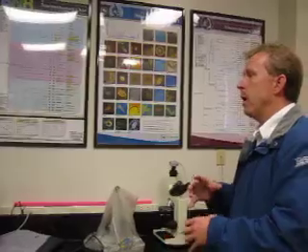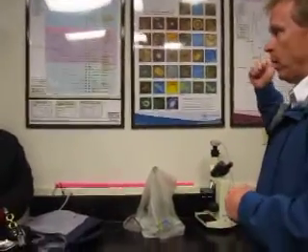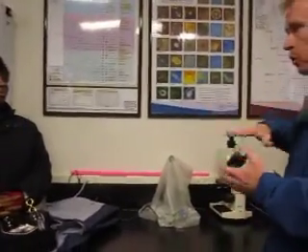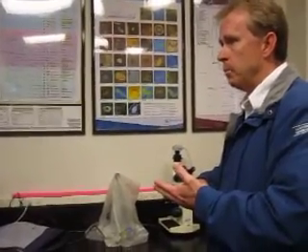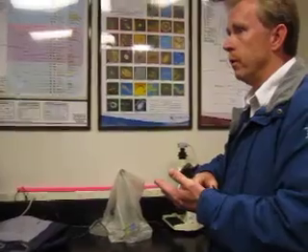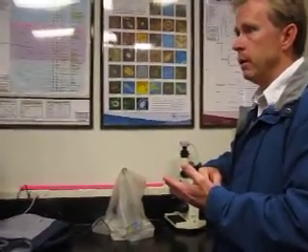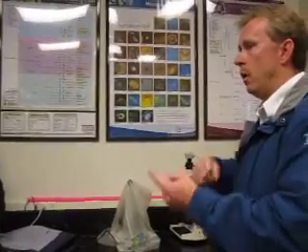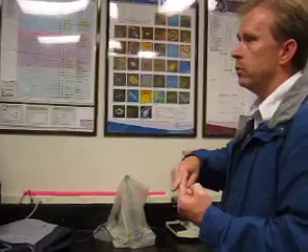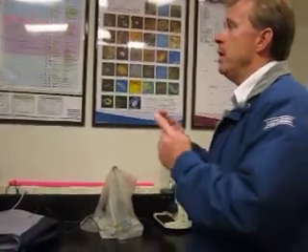So we want to break down that ammonia. How do we do that? We got microbes that we grow out there in the basins in the biological process. There's 2 of them: Nitrosomonas and Nitrobacter. The Nitrosomonas will convert ammonia to nitrite. The Nitrobacter will convert nitrite to nitrate. Then we run the whole system in the biological process through a denitrification process where nitrate is converted to what?